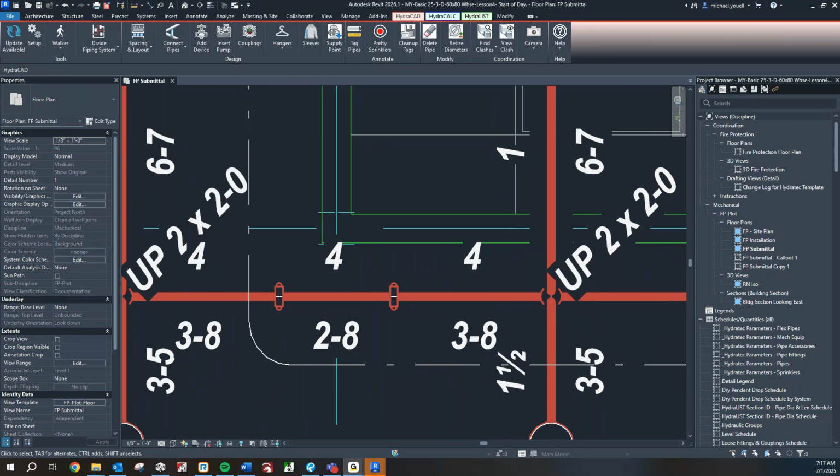If we were using dynamic centers or dynamic lengths, would it automatically update? Yes, it would. There's two downsides to dynamic. One is that it's ugly, and you can get over that easy enough. The other one is that it's the actual length of the pipe. So it'll serve as a substitute for the cut lengths, but it won't serve as a substitute for the center to center lengths. And on this pipe, they happen to be the same, but move to the right.